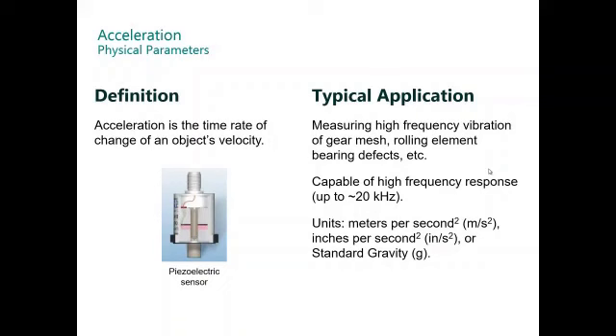Acceleration is the time or rate of the change of an object's velocity. This is specially designed for high frequency. One example of high frequency is measuring gear mesh or rolling element bearing defects. The measurement is capable of measuring high frequency up to 20 kilohertz, and the units are meters per second squared or g's. The inches per second squared is not common. It's preferred the g's or standard gravity measurement.